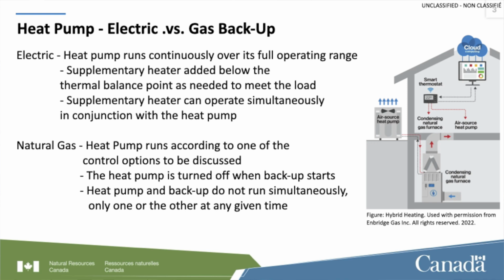With an electric system, the heat pump runs continuously over its full operating range, and the electrical resistance coil is just there to back it up—these run simultaneously. When we get into a natural gas situation, the gas will kick in and disconnect the air source heat pump. These two do not run at the same time.